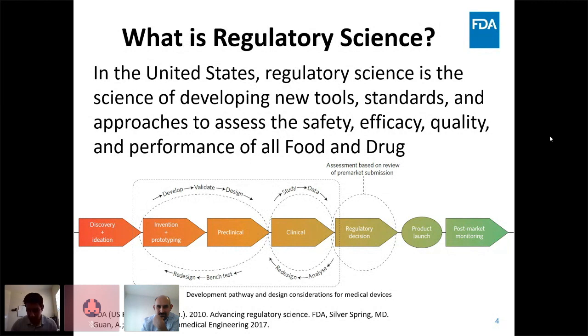It is important to start interacting with the agency as early as possible, even during the research and developmental stage. Imagine you change some material in the middle of the preclinical testing, and you don't let FDA know or get feedback from FDA. Then you spend a lot of money on biocompatibility and animal study, etc. After you submit, you figure out that the biocompatibility, for example, had been done on the previous version of the device, not the device with the new materials. That's a big problem, because FDA would probably ask you to redo all those expensive tests. So it is very important to have an interaction with FDA and get feedback on a regular basis.